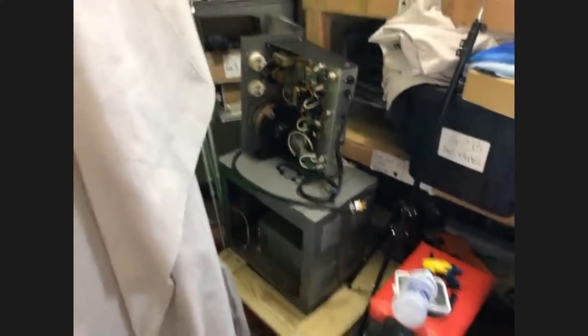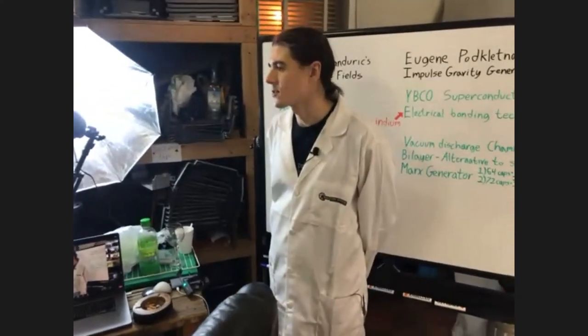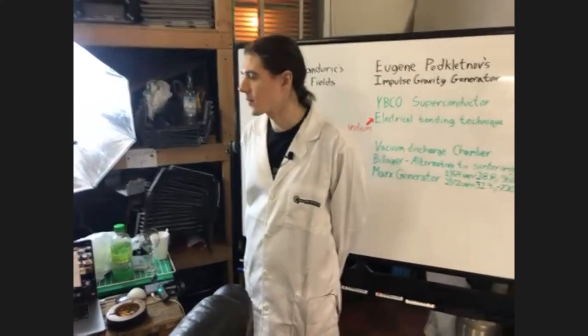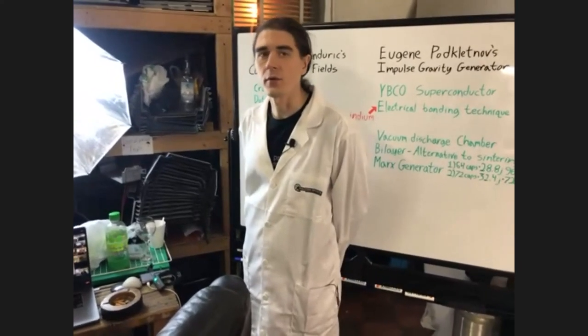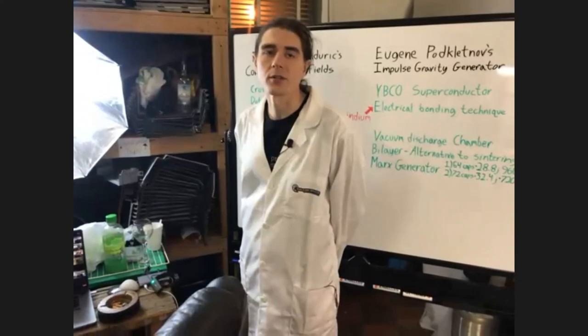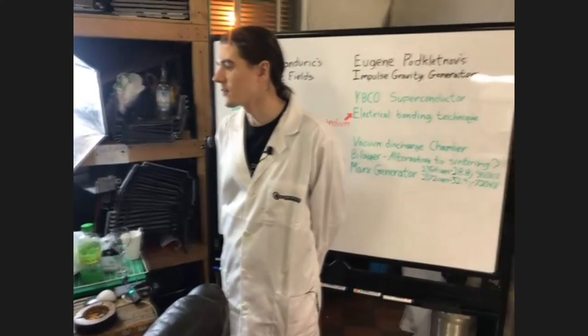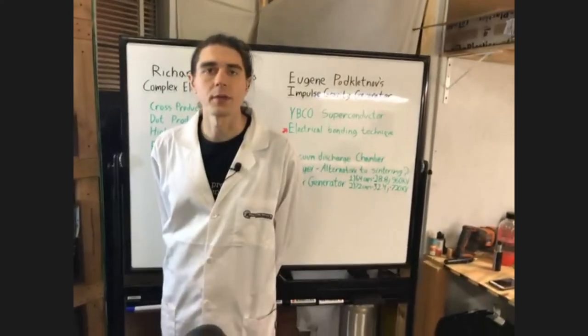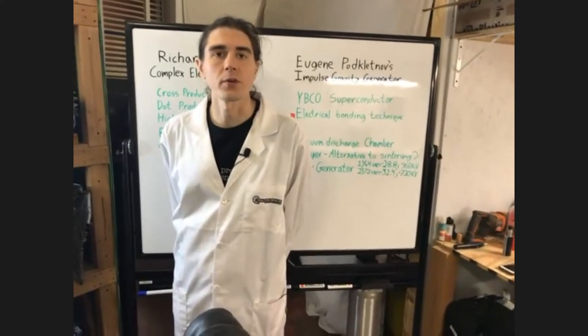At its core, all that thing really is, effectively, is a voltage divider for some meters and current, a variac, and a huge plate transformer with multiple wiring configurations. All we have to do is give that variac power to feed the plate transformer. The rectifiers are already in place and everything else should work straightforward. There's no reason we need an interlock in that system if we're going to install it in a cabinet and bring out external cables anyway.